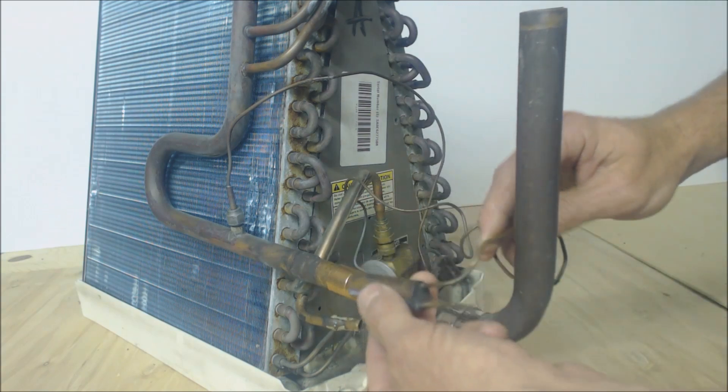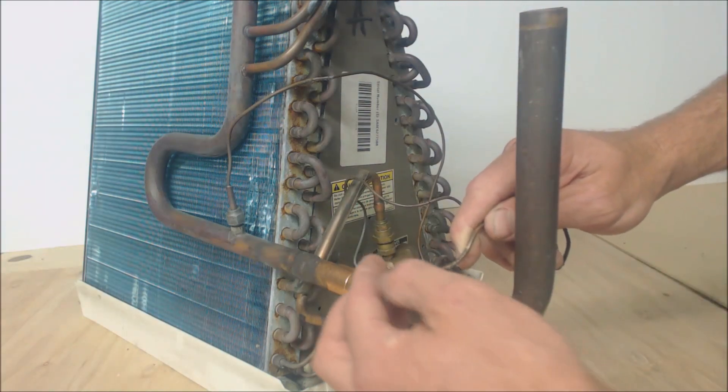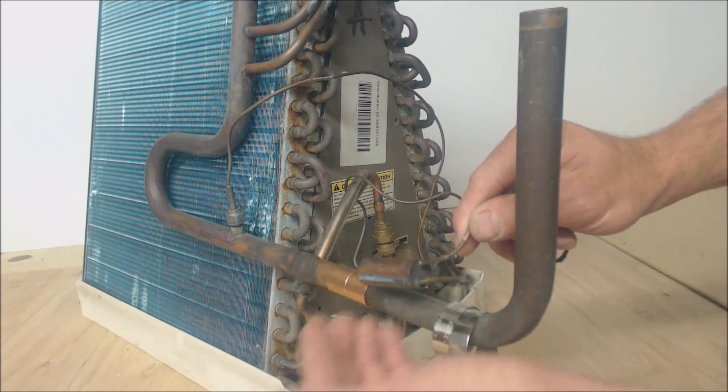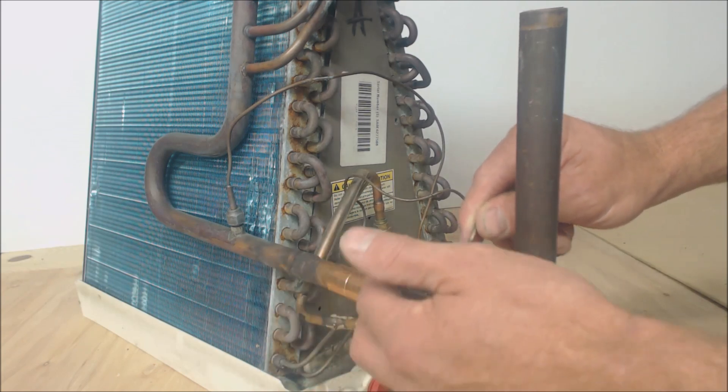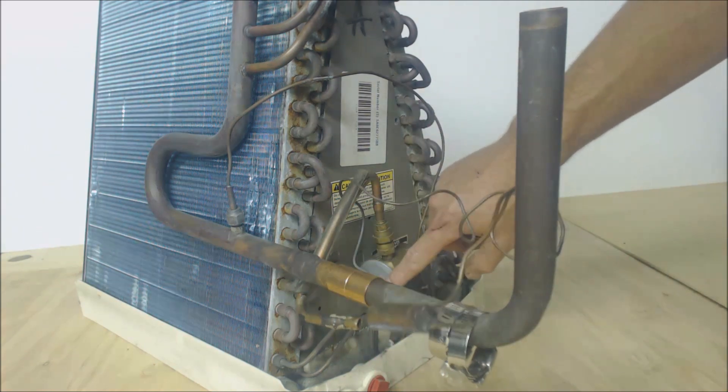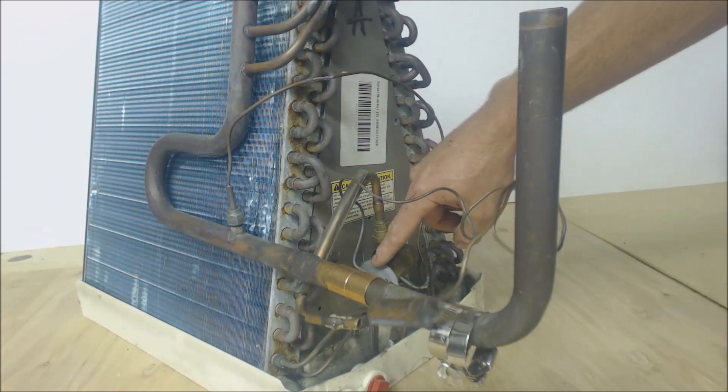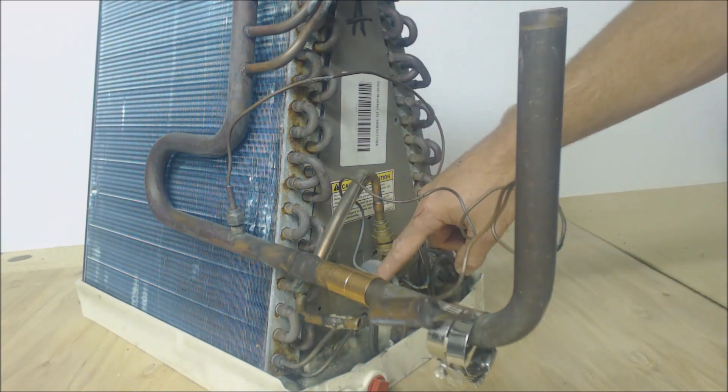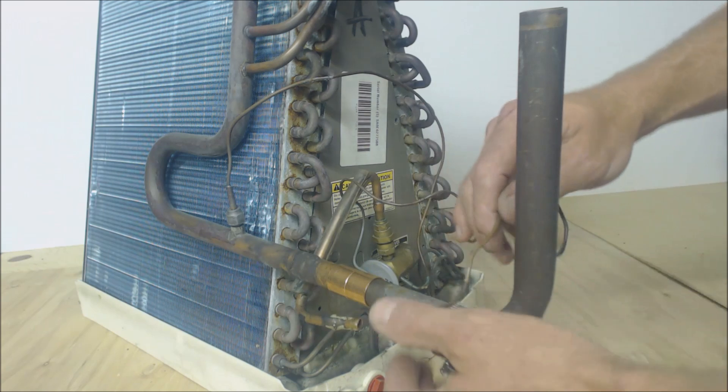All it's really doing is there's refrigerant inside the sensing bulb. When it's cooler, it applies less force on the TXV to open the TXV. When it's hotter, it applies more opening force on the TXV.